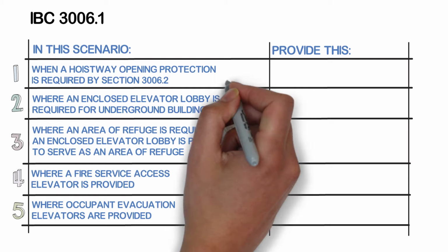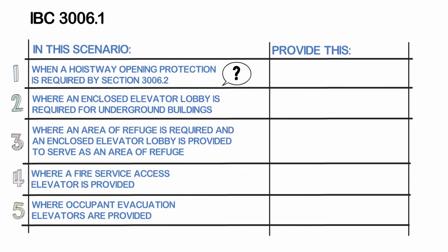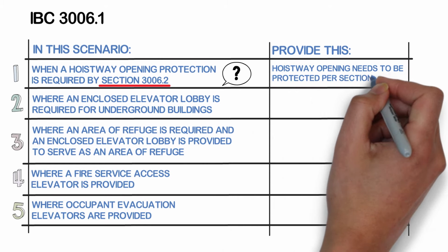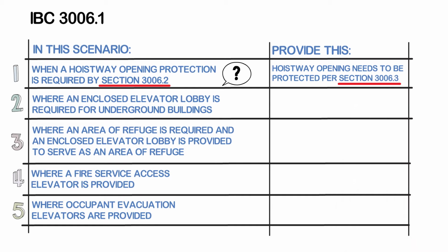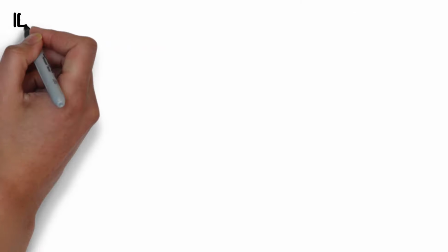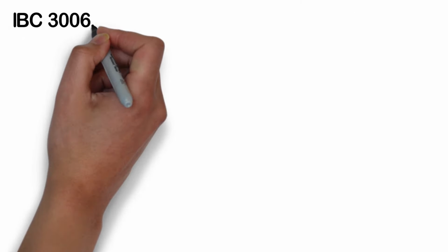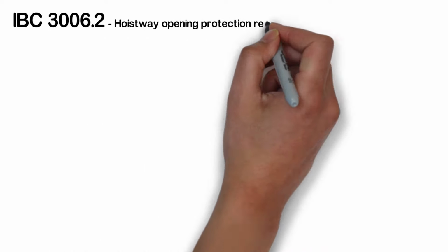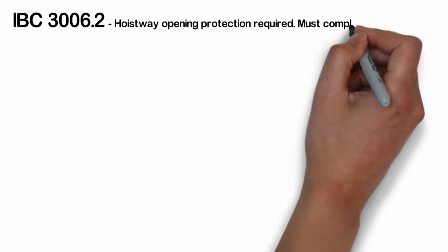To address this scenario, first, we need to answer the question, when does Section 3006.2 require a hoistway opening to be protected? This is important because if the hoistway opening needs to be protected, then it needs to be protected per Section 3006.3, and you guessed it, one of the ways of protecting the hoistway is by providing a rated elevator lobby.